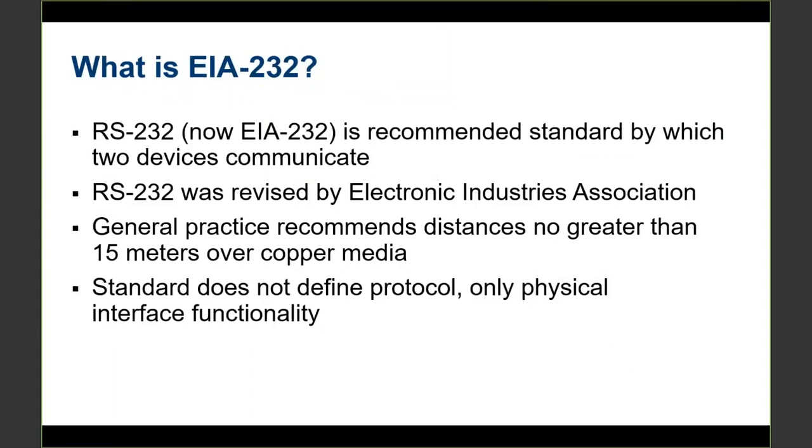But the general rule of thumb to remember is you don't want to go, generally speaking, longer than 15 meters or 50 feet over copper medium. You can go much further over fiber optics, but when we're talking about 232 communications over copper media, we're talking about a 50 feet limitation. That's what we recommend.